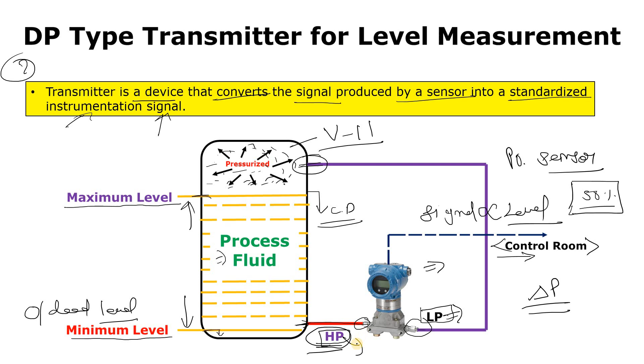Now see here, this is my transmitter. Within that transmitter there will be one pressure sensor. That pressure sensor may be diaphragm type, capsule type, or strain gauge type, etc. It depends on the application, and it is used to measure the differential pressure. I hope you got my point.